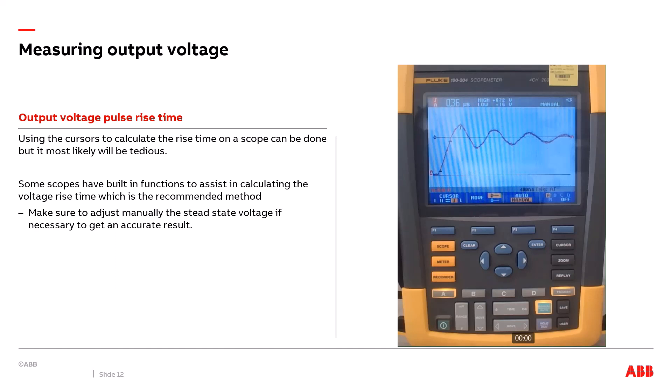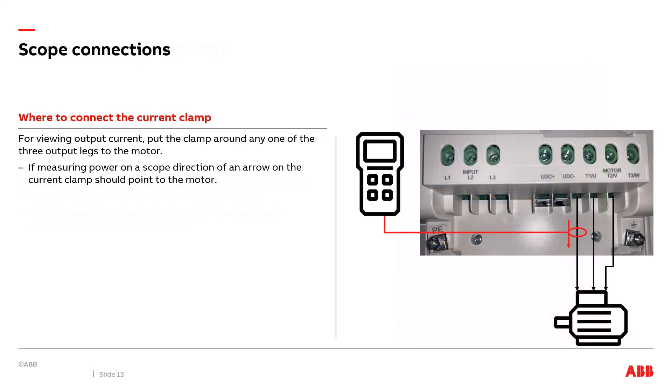The good news is MG1 Part 31 states the minimum rise time of an IGBT shall be 0.1 microseconds. In this case, I'm at 0.37 microseconds — much greater than 0.1 microseconds — showing a good result and that this VFD will not be damaging the motor. Now I'll transition to discuss what the current waveform looks like between the drive and the motor on an oscilloscope.